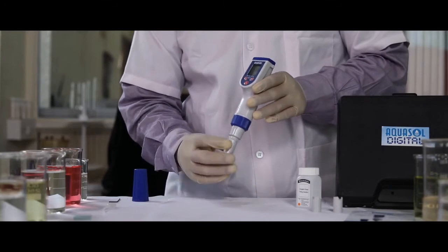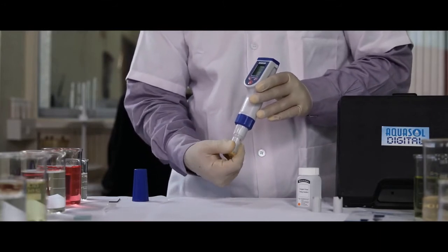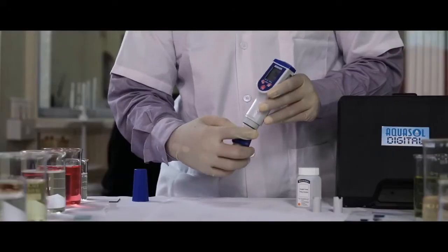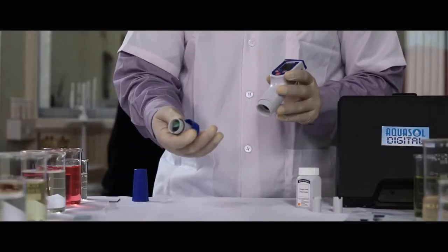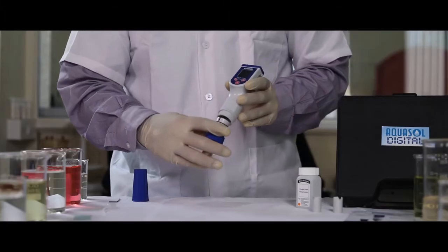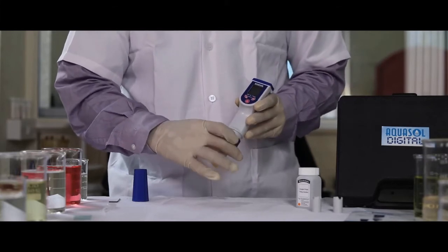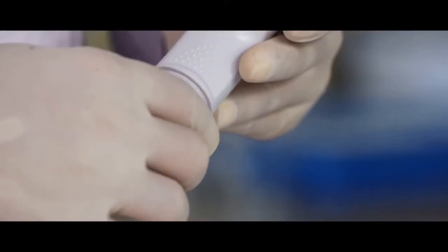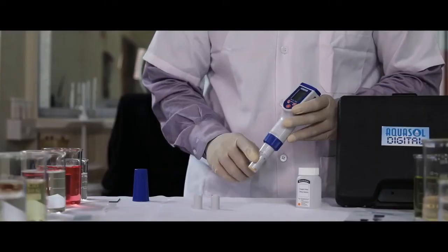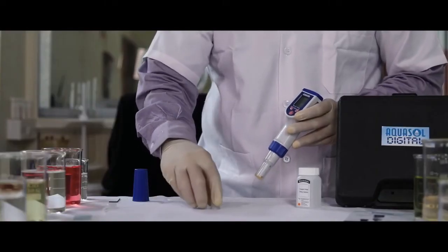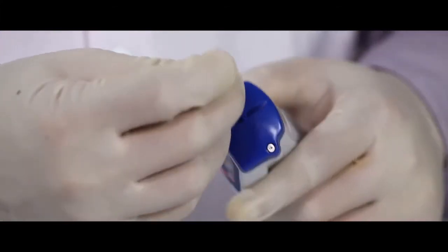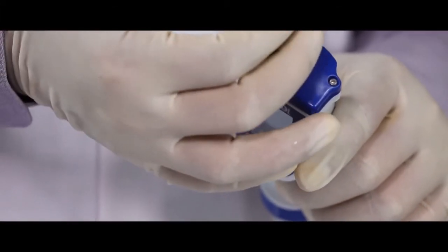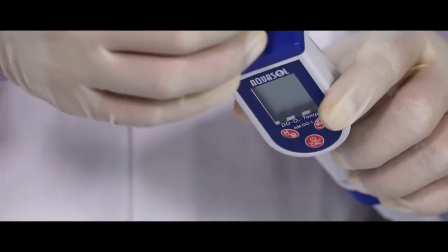Recap the soaking bottle cap to secure the electrode. Make sure it is wet. To replace the electrode, unscrew the electrode collar, separate the electrode and replace it. We do provide an extra membrane cap along with the meter. Batteries are located on top of the meter. Note the polarities and replace the batteries.